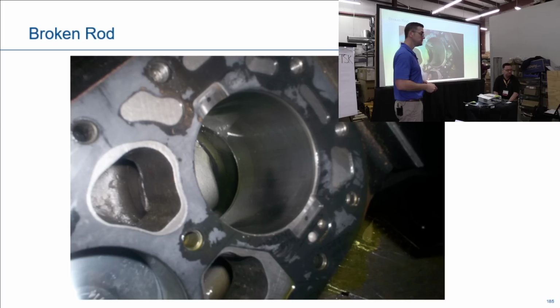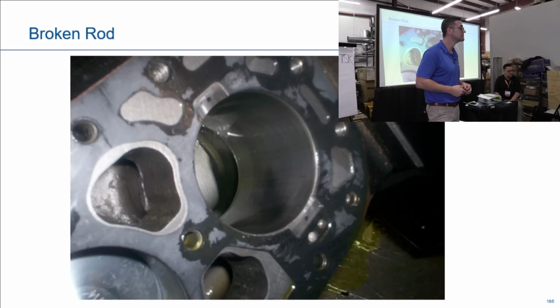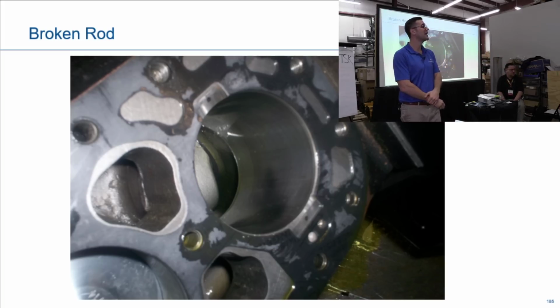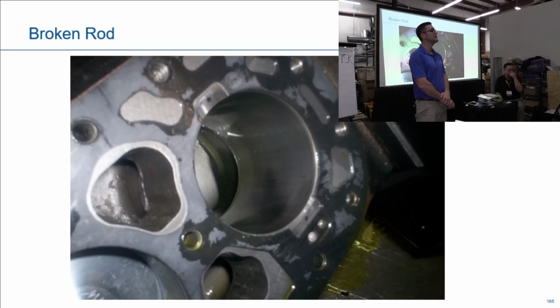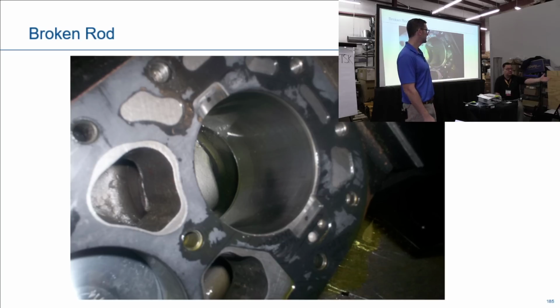I've seen a piston broke in half, and that was one where they replaced the compressor twice. Oh, so until they retrofitted the whole system, but it was old Carlyle. Yeah, they did it twice. So what could have been? What broke the rod? A slug, right? And that's a perfect example. What he said was they replaced the compressor twice.